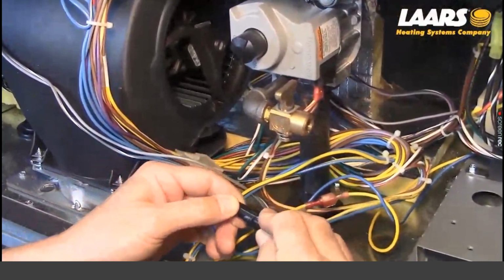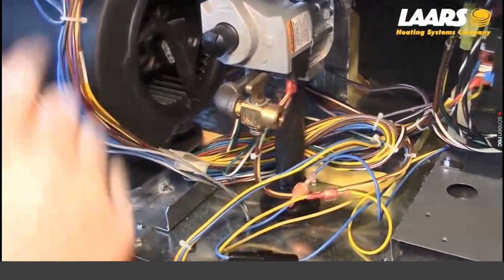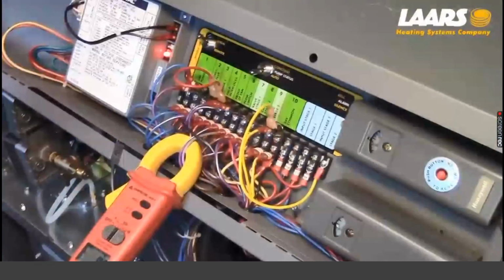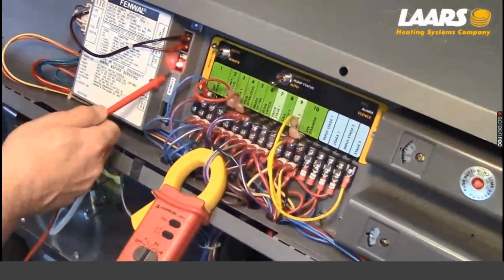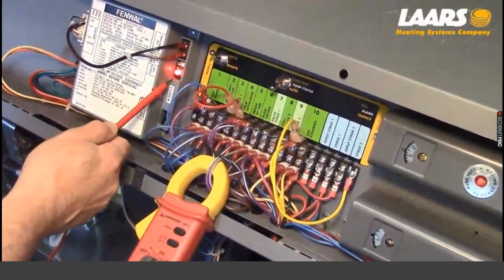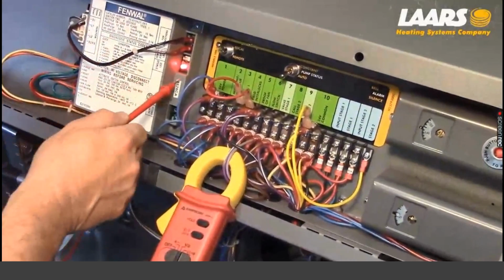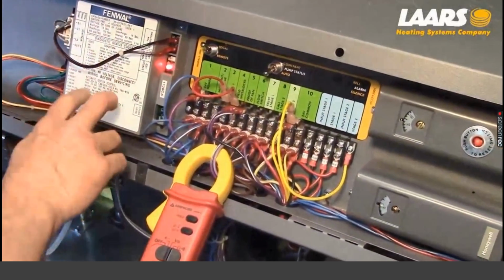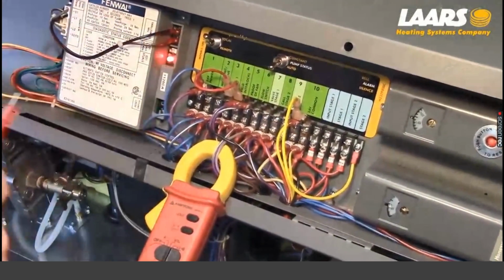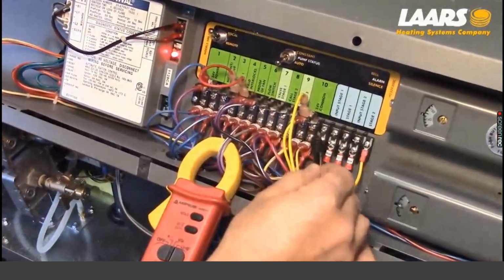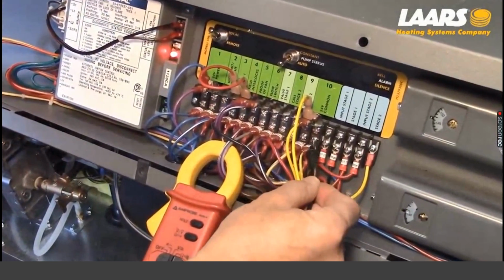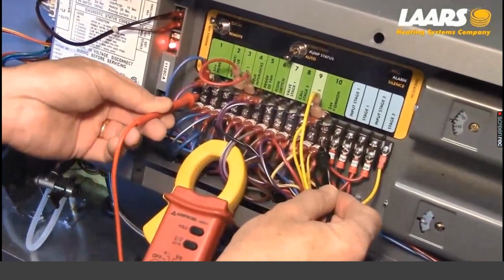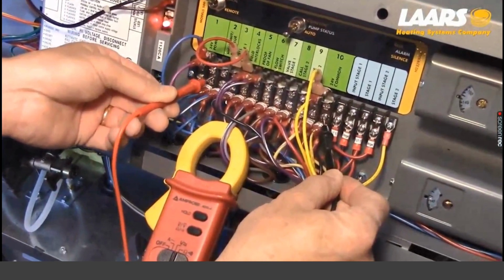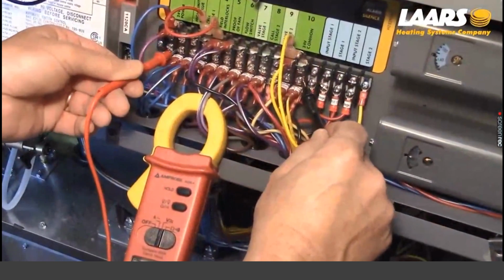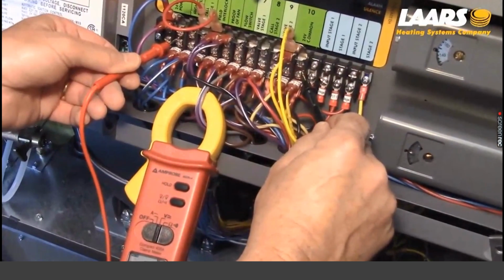I'll put this back in, and now we're going to go back to the terminal strip. And I also want to show you, now you can see there's an LED light here on the Fenwal ignition control. So I know I have 24 volt power, but we're going to check it anyways. Start with one meter lead on 24 volt common. Over here I can either go to terminal 1 or terminal 2. You can see I'm reading 25.1 volts on either one of these terminals.